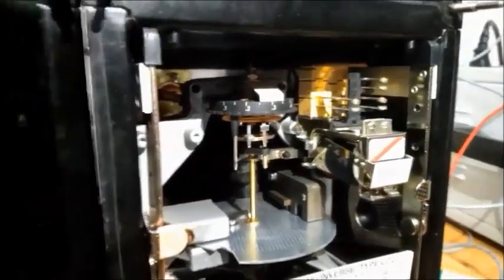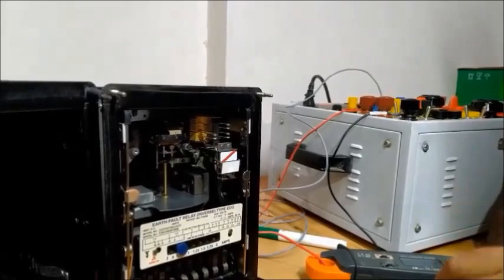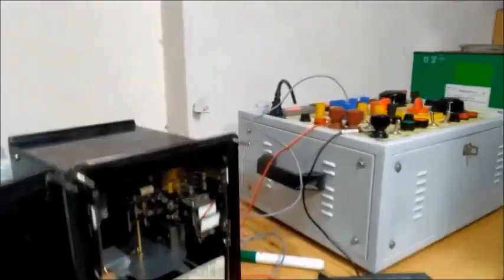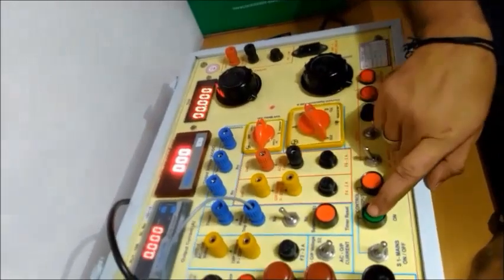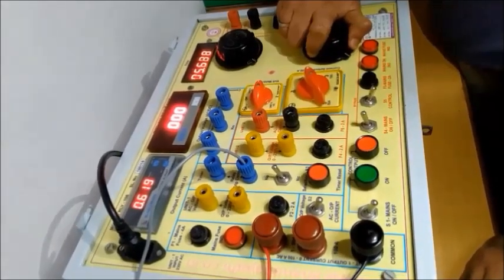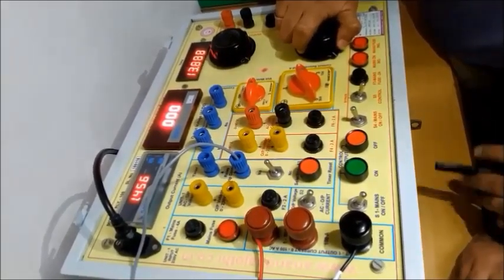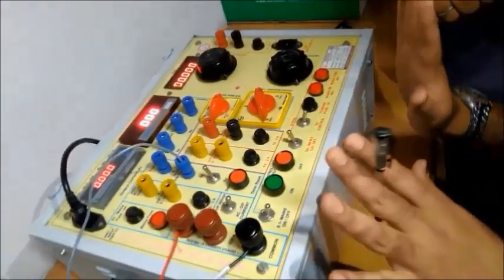So now we are going to create our fault. So fault is, now we are injecting 2 times of our set current. So fault current is 1.5 amps. Now we are injecting here. So okay, start fault simulation kit. And set the current is 1.5 amps here. Just set. Okay, we already set. Okay, start 1.5 amps. Okay increase. Just set 1.5 amps and stop.